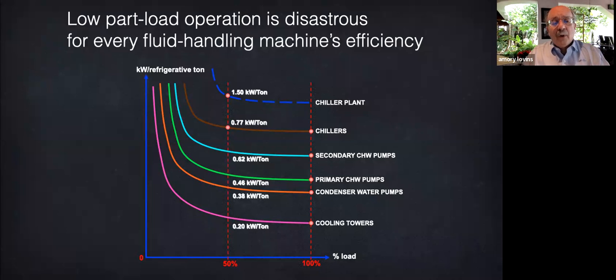Now, if the load varies widely, you should spec pumps with a big bullseye or optimize them with ASDs, adjustable speed drives, which help compensate for prevalent oversizing even at constant flow, so you can trim them back to just the right speed. Or consider multiple pumps, often of different sizes, what's called multiplex unequal. Each pump is optimized for a particular piece of the load curve, so you can operate that when you need it. And of course, the ASD eliminates the old throttling valve, the stupid way that much flow is still controlled.